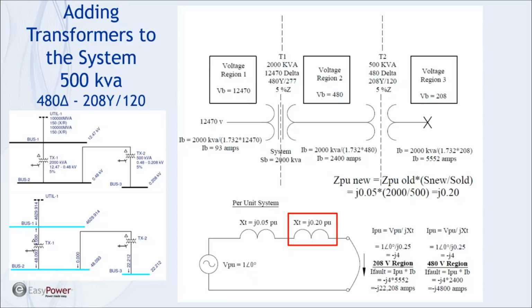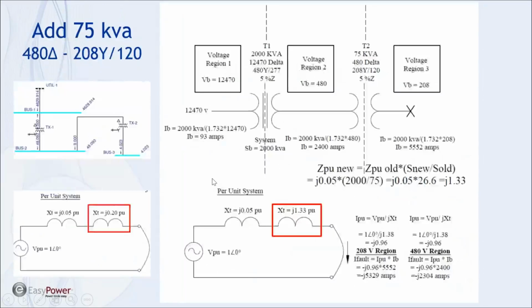The other thing I wanted to do, which I thought was a good example, is it's real common to get a call from somebody when they need to add a low voltage, less than 250 volts, 240 volt, 208 volt, 200 amp panel. And a typical design like that tells me that we're probably going to need to set a 75 kVA transformer. 200 amp, 225 amp distribution panels are very common. And so that's a scenario that we might be looking at. So we set this 75 kVA transformer into this system, and here's what happens.